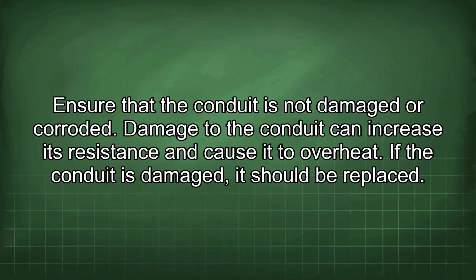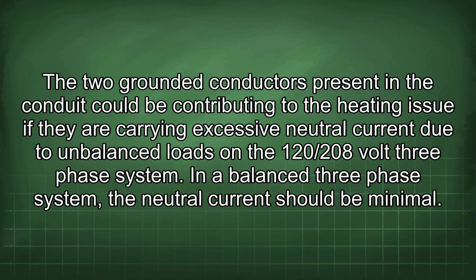Ensure that the conduit is not damaged or corroded. Damage to the conduit can increase its resistance and cause it to overheat. If the conduit is damaged, it should be replaced. The two grounded conductors present in the conduit could be contributing to the heating issue if they are carrying excessive neutral current due to imbalanced loads on the 120/208 volt three-phase system. In a balanced three-phase system, the neutral current should be minimal.